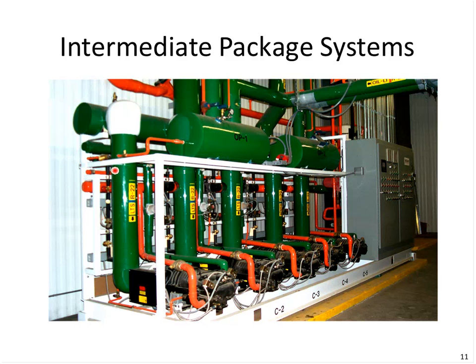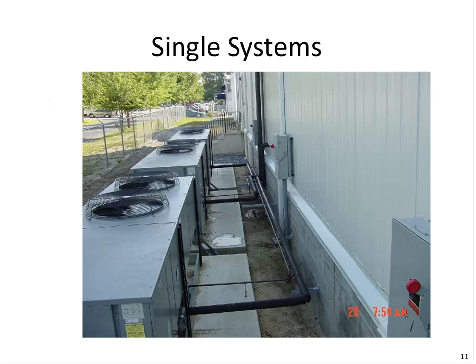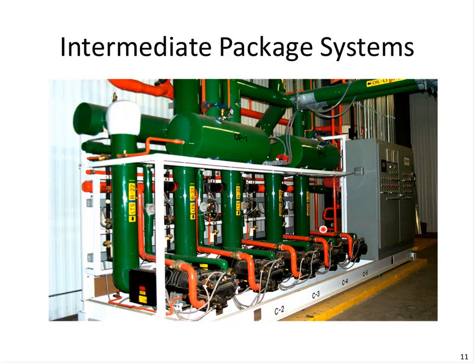We can see here R22 today might be using an alternative like R422D or 507, some other halocarbon refrigerant. Although these packages could be ammonia, they typically wouldn't be. Although with the advent of a microchannel condenser, we may see ammonia showing up in package systems like this. Wouldn't be surprised to see that soon because we have a single component microchannel all aluminum condenser for intermediate packages.